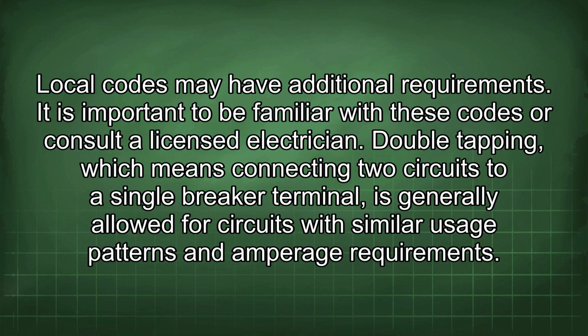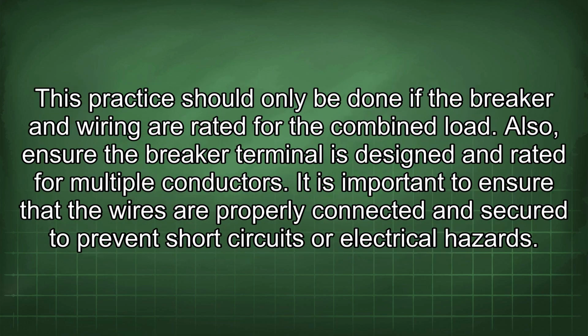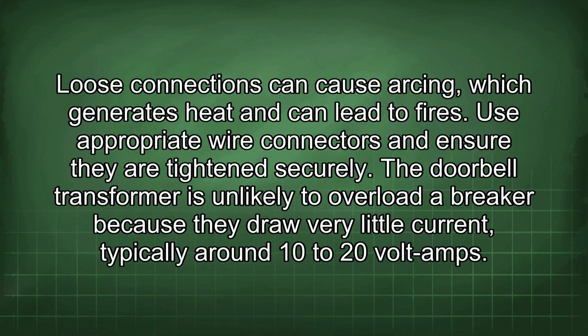Double tapping, which means connecting two circuits to a single breaker terminal, is generally allowed for circuits with similar usage patterns and amperage requirements. This practice should only be done if the breaker and wiring are rated for the combined load. Also, ensure the breaker terminal is designed and rated for multiple conductors. It is important to ensure that the wires are properly connected and secured to prevent short circuits or electrical hazards. Loose connections can cause arcing, which generates heat and can lead to fires. Use appropriate wire connectors and ensure they are tightened securely.